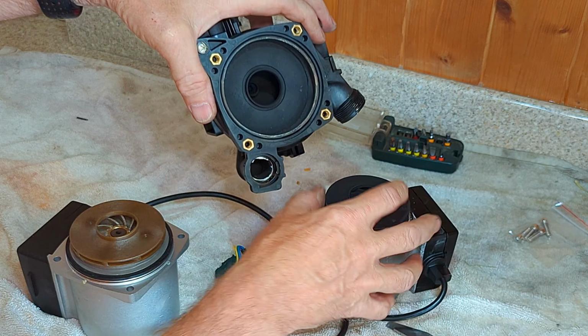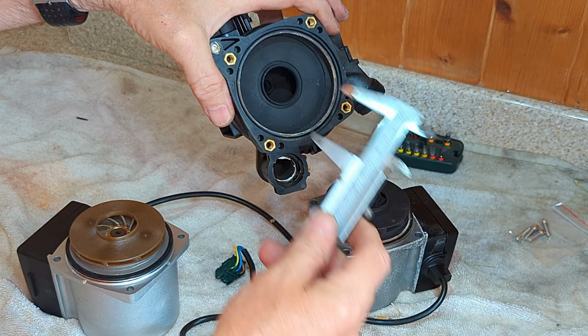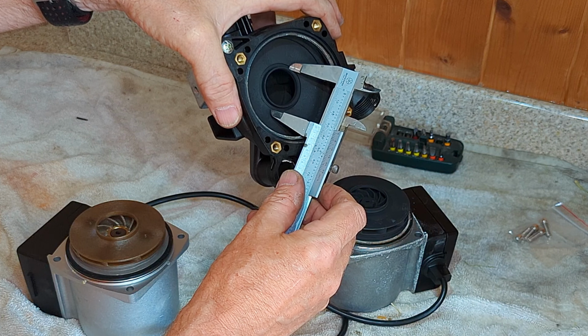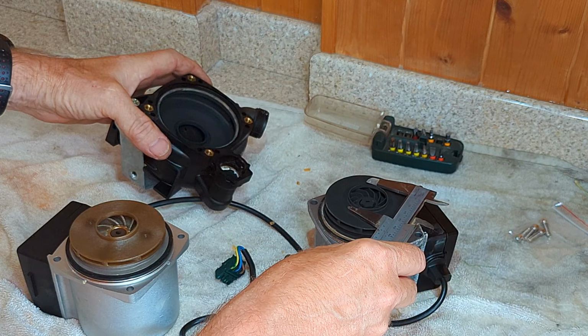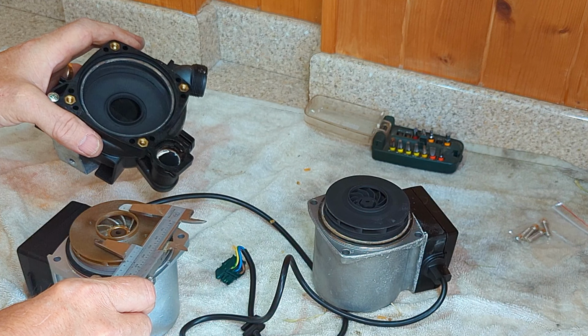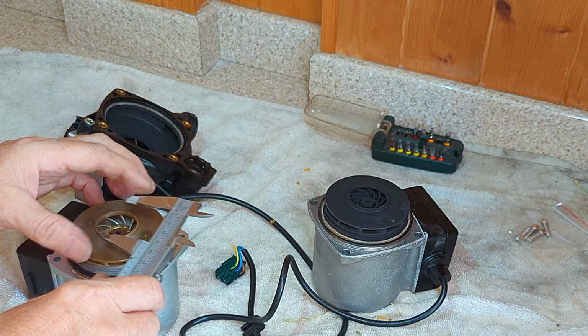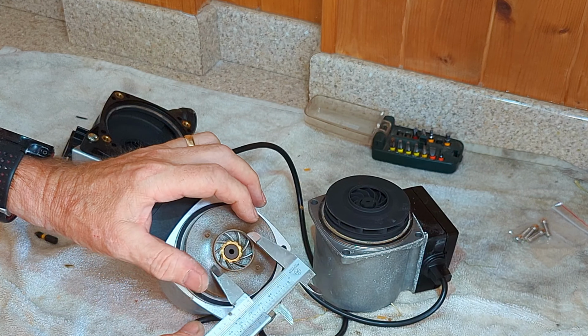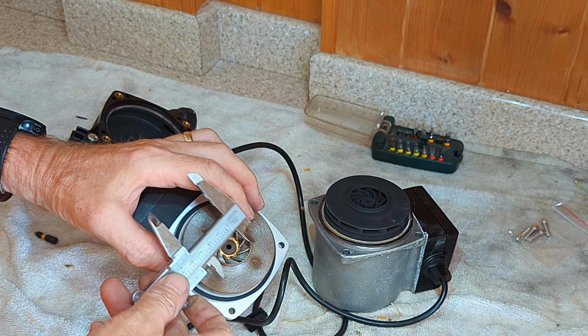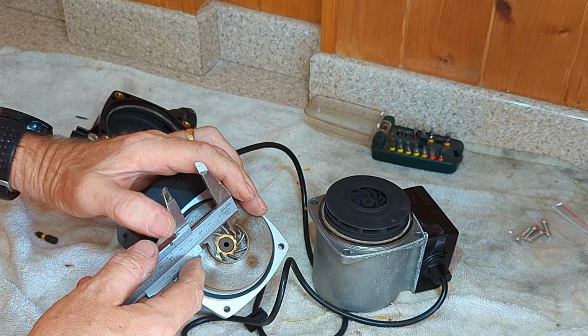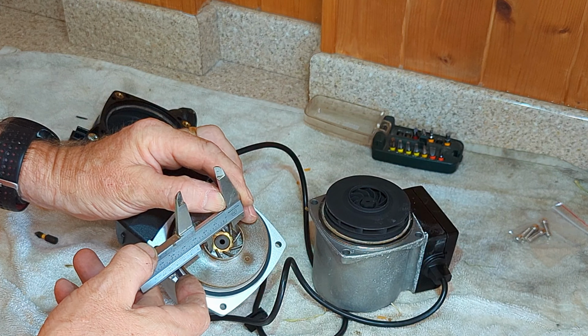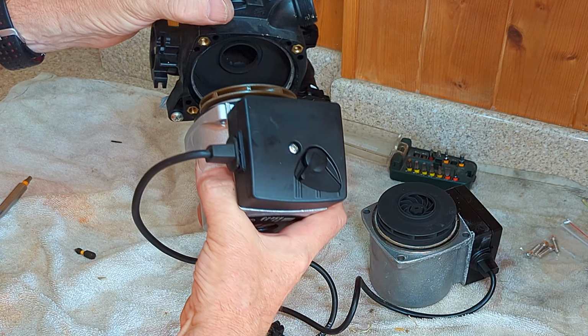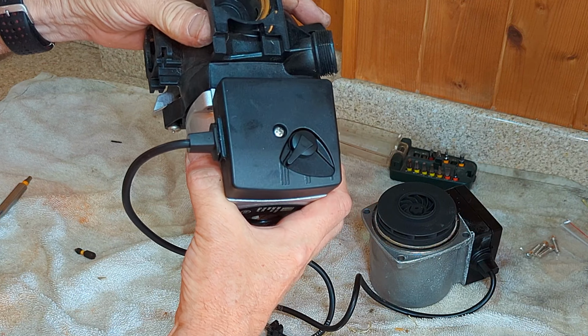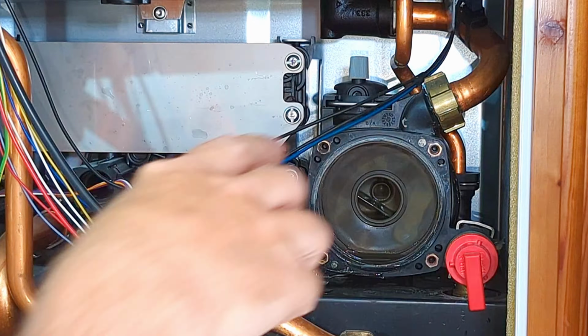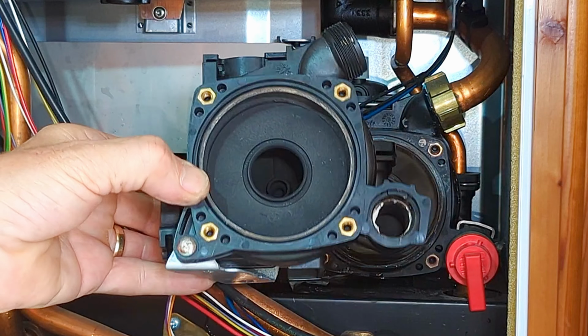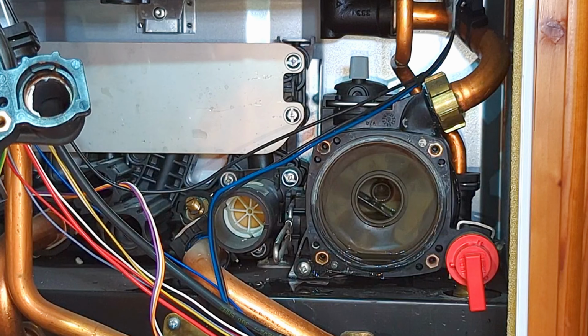Now once again, there's a slight difference between the inner size of the impeller. You can see there it's the same fit there, and on this BritTherm one it's slightly smaller. But once the pump was fitted, it didn't seem to make any difference. Maybe you lose a little bit of efficiency, but then maybe it makes no difference at all. And you can see how this BritTherm pump head fits nicely onto the Vaillant pump housing. And if you look at these two pump housings, you can see they are exactly the same.